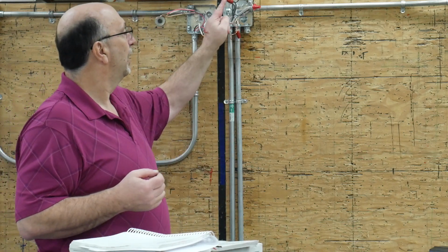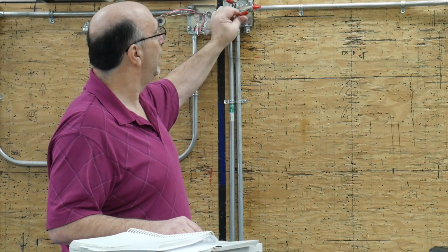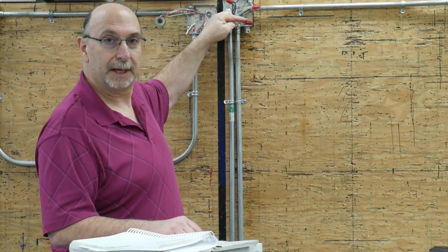Sub-rule B, we have to take one insulated conductor for every pair of connectors with insulated caps. No deduction for one conductor connector, and deduct one insulated conductor for 2 or 3 connectors, 2 insulated conductors for 4 or 5. So what that's referring to is, obviously these wire nuts right here take up room within the box. So sub-rule B helps you out to determine how many conductors you have to add for these wire nuts.